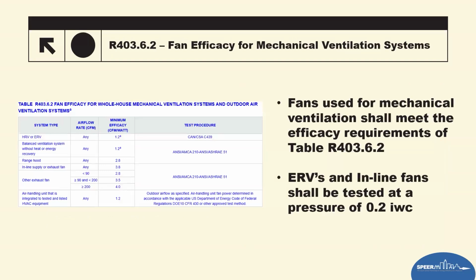Starting in 2018 and moving forward, we now have a fan efficacy table for mechanical ventilation. Any fan that's used as its fan source for bringing in or exhausting air for mechanical ventilation reasons must actually hit a fan efficacy, which is CFM per watt, using this table. Looking at the very bottom, in the 2021, they added the air handler unit that is integral and tested and listed as part of the HVAC equipment. Any CFM must hit a 1.2 CFM per watt draw. So the third parties are going to have to test that to verify that it's being done. There are equipment manufacturers that can meet that, but it's very hard to do.